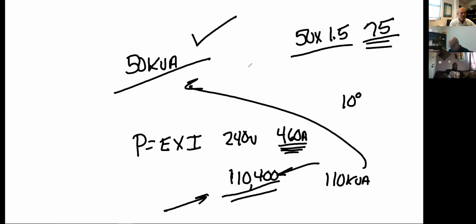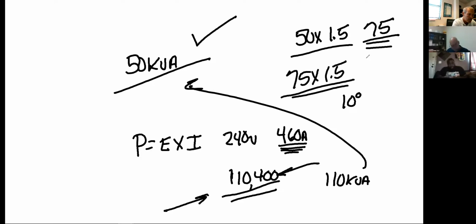You're putting a transformer there that will do what? 150%, right, which is what? 112,500 - 112.5. Right, you have deduced this is severe for where I live, it's the dead of winter, this is going to be the worst it ever gets. So I'll go ahead and put a 75 there, not 100, because it will go to 112.5 kVA.